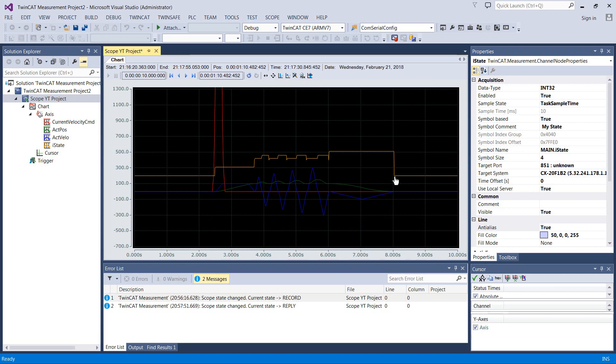So you can really use this to visualize machine cycles and find out like any long section like this. You can go and say, well, what is taking that long? Does it match my design time? Is there something going wrong? Is there a sensor it's waiting for that it only needs to see briefly? You know, all that sort of stuff you can figure out with these graphs. So hopefully that's pretty obvious how useful this can be.